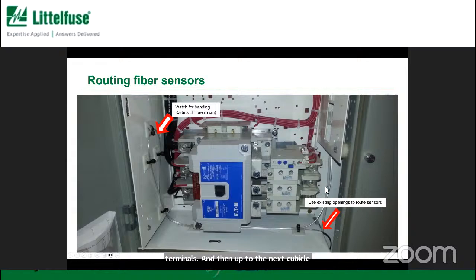In an MCC, or somewhere where you have many small compartments, another option is to pull the fiber through those compartments. We just ask that the bending radius is about 5 centimeters on the fiber. If you pinch it too tightly, then light can escape. But our fiber is very rugged, very robust for a fiber optic cable, and so it is very easy to work with, but we do ask for about that 5 centimeter bending radius.